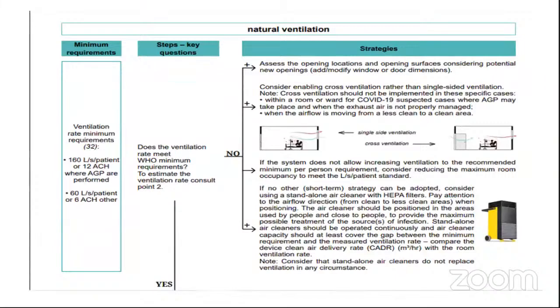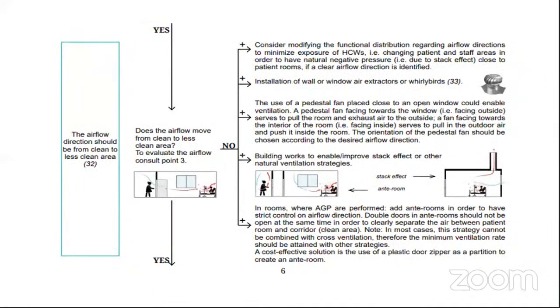In case they are meeting the requirement, we go on to the next query: does the airflow move from clean to less clean area? If it does, well and good. If it does not, we need to work towards it by installing a wall air extractor, using a pedestal fan outside, or enabling the stack effect in rooms where aerosol generating procedures are being performed, and providing an ante-room. The double doors of the ante-room should not be opened at the same time, so that we are able to barricade the infected person and not take the virus outside of the ante-room.